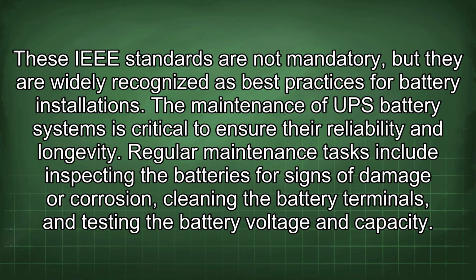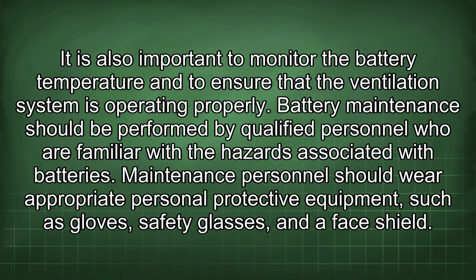The maintenance of UPS battery systems is critical to ensure their reliability and longevity. Regular maintenance tasks include inspecting the batteries for signs of damage or corrosion, cleaning the battery terminals, and testing the battery voltage and capacity. It is also important to monitor the battery temperature and to ensure that the ventilation system is operating properly.